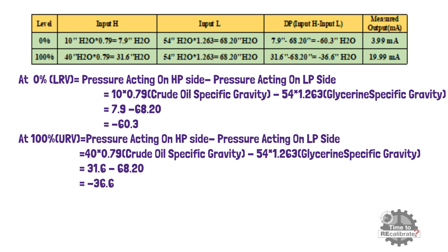Now let's understand the table for 100% level. At 100% level, the DP transmitter input high side has 40 inches H2O pressure, multiplied by the specific gravity of crude oil which is 0.79, giving 31.6. Here, 40 inches is the total distance from the transmitter to the 100% level. So the DP transmitter high side has 31.6 inches H2O pressure at 100% level. Similarly, the DP transmitter low port side has 54 inches H2O pressure, multiplied by the specific gravity of glycerin, giving 68.20. So the transmitter low port side has 68.20 inches H2O pressure at 100% level. Differential pressure is minus 36.6 inches H2O at 100% level.